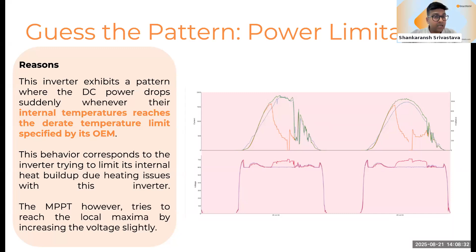power limitation. What happens here is the internal temperature: the fan of this inverter had stopped functioning. So the internal temperature of the inverter was rising to almost its derating temperature, which was 60 degrees Celsius. Whenever it approaches that limit, the inverter starts to limit its power to limit the heat being accumulated inside. But if that limit is breached, the inverter will turn itself off, and then start back again. So that's a classic inverter heating problem. In extreme cases, when it reaches the derate temperature, its power gets limited, and eventually the inverter trips. I think that gives a fair idea of how we do what we do.